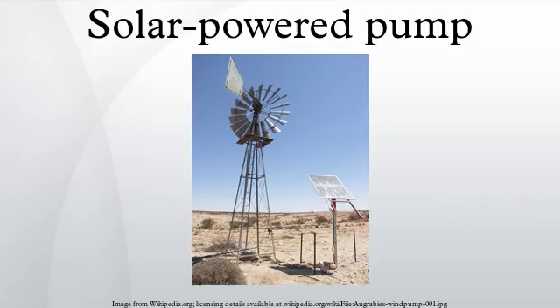The purpose of the controller is twofold. Firstly, it matches the output power that the pump receives with the input power available from the solar panels. Secondly, a controller usually provides low-voltage protection, whereby the system is switched off if the voltage is too low or too high for the operating voltage range of the pump. This increases the lifetime of the pump, thus reducing the need for maintenance.